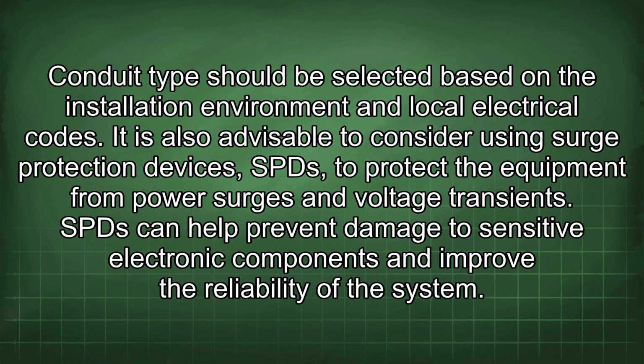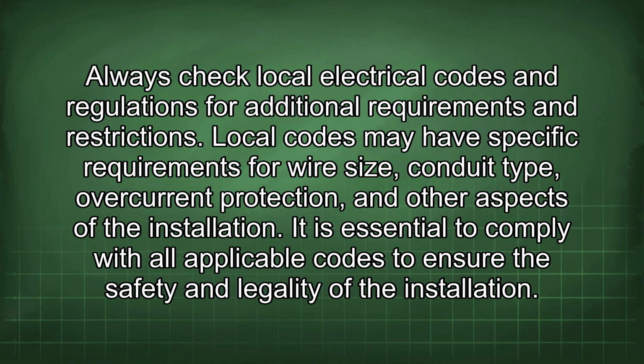It is also advisable to consider using surge protection devices, SPDs, to protect the equipment from power surges and voltage transients. SPDs can help prevent damage to sensitive electronic components and improve the reliability of the system. Always check local electrical codes and regulations for additional requirements and restrictions. Local codes may have specific requirements for wire size, conduit type, overcurrent protection, and other aspects of the installation. It is essential to comply with all applicable codes to ensure the safety and legality of the installation.